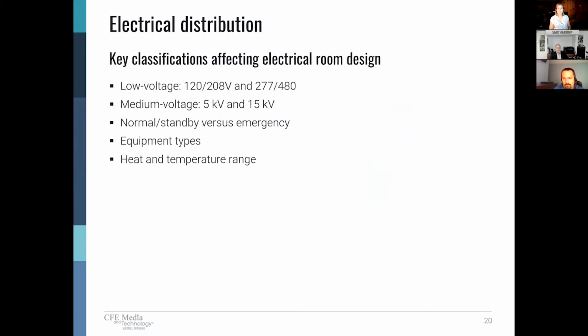So the key classifications, when we go back, we talked a little bit about the different types of systems, types of gear. The key classifications affecting how you're going to lay out the electrical room. Are you doing low voltage? We saw the table with the different clearances based on voltage. Are you doing medium voltage? That brings in an increase in that working space, not necessarily in the dedicated, but in the working space clearances. Are you doing normal, standby, or emergency? James mentioned this. Emergency rooms are completely different requirements than just a standard normal power room in terms of what can be in there and what cannot be in there, and the types of fire protection. Also, equipment types. We're going to talk a little bit about types of equipment and how that affects the electrical design. We've already briefly touched on that. And then the heat and the temperature range of the space.